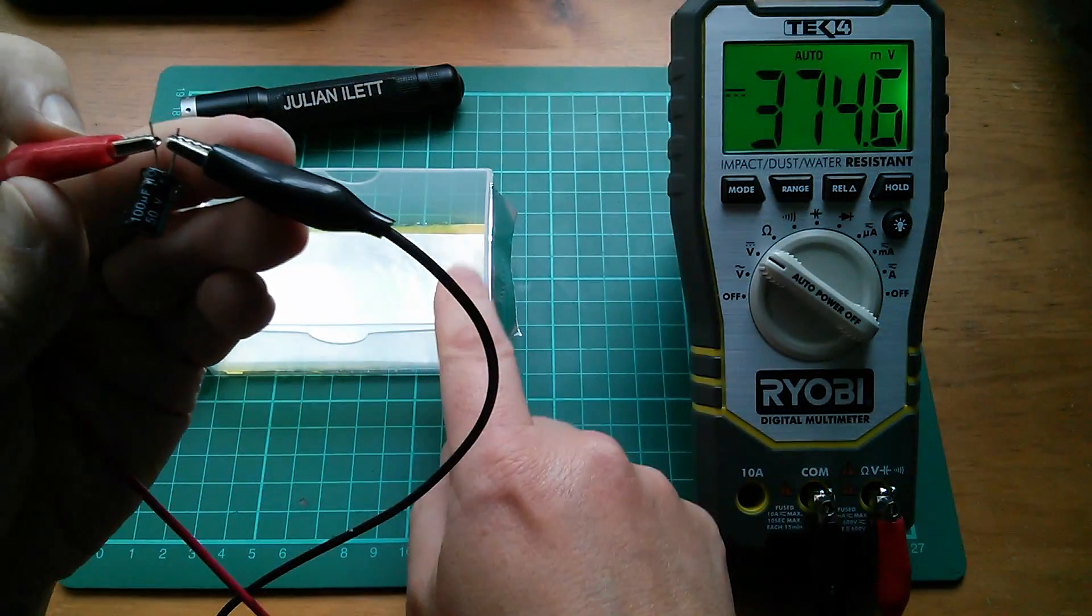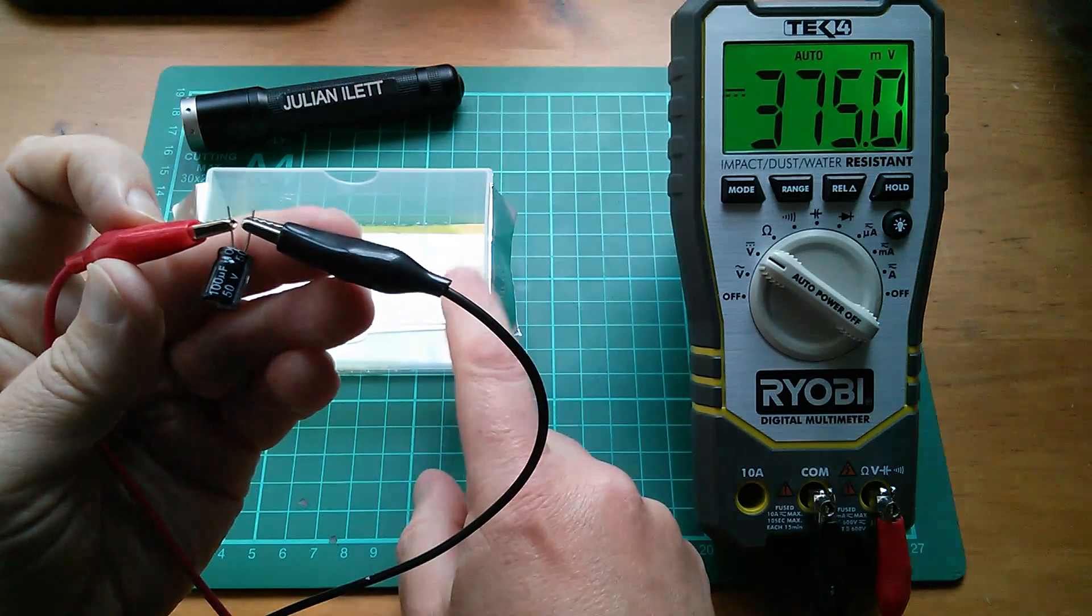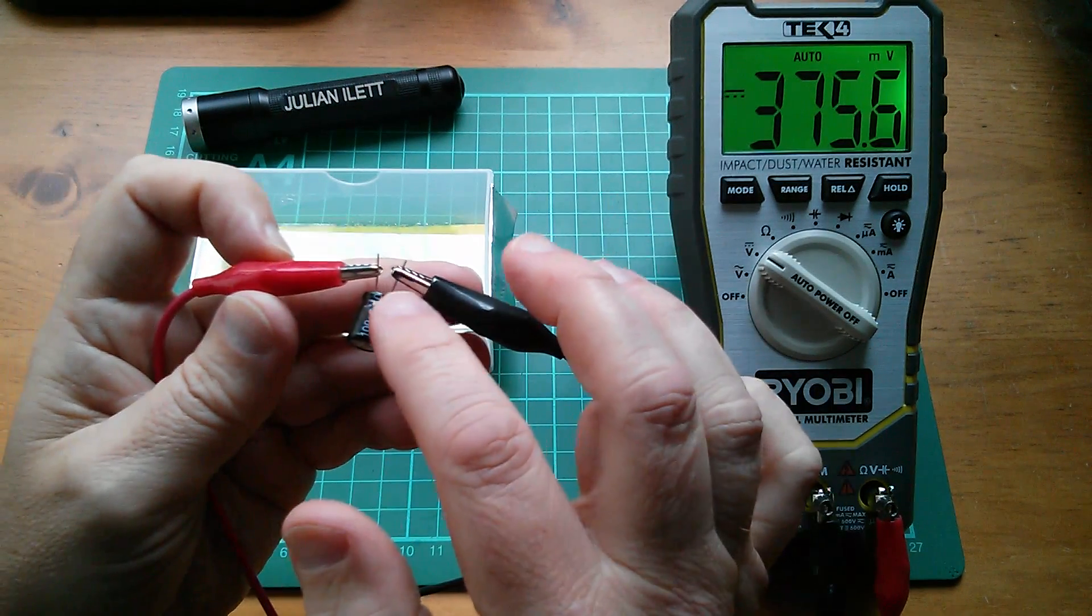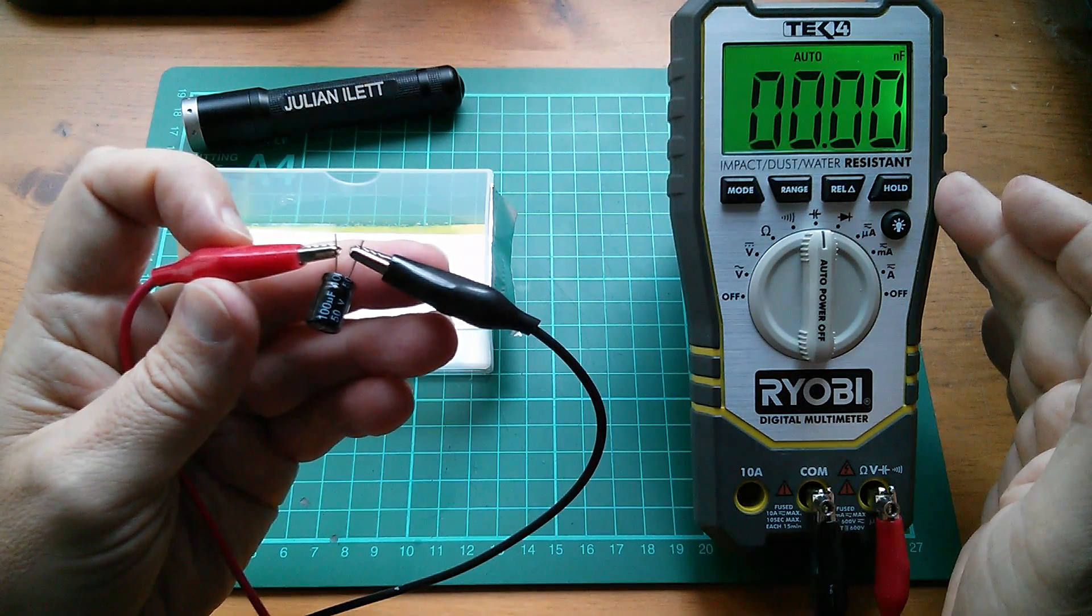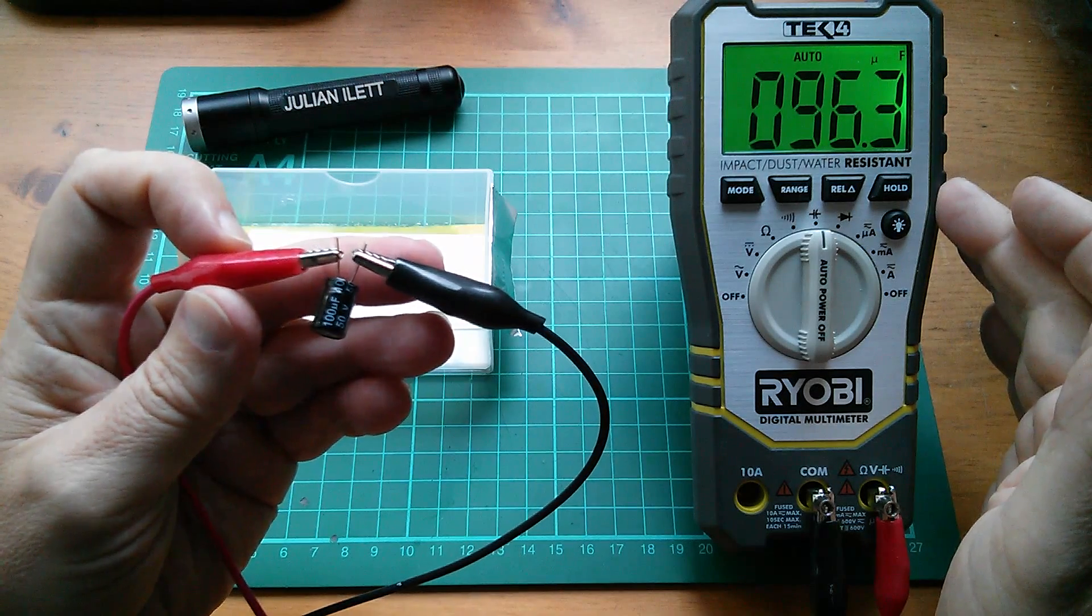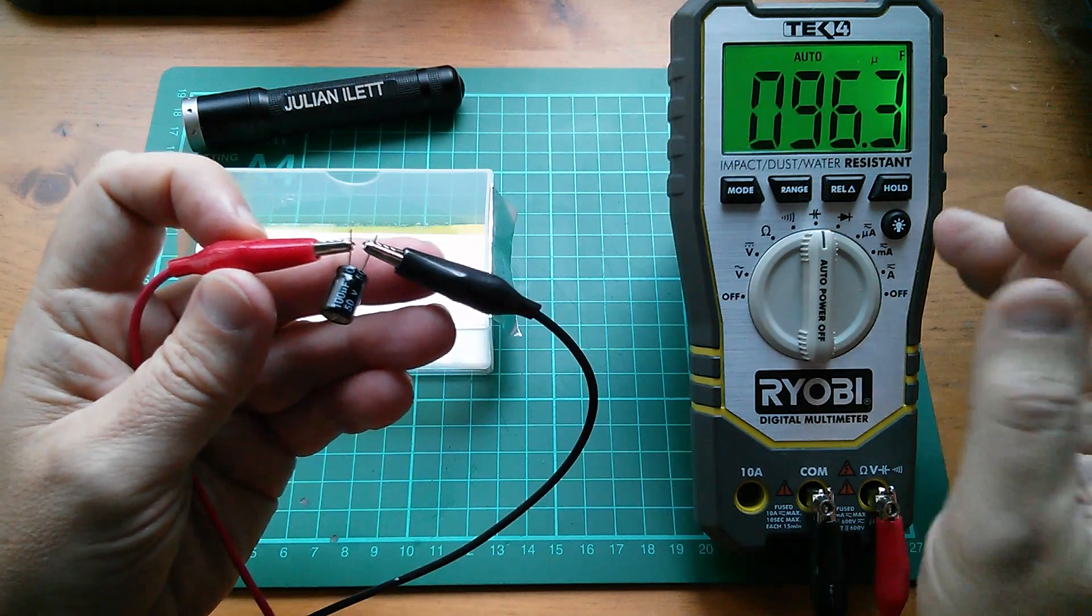But if this capacitor is genuinely a similar value, 60, 70 microfarads. And this is 100 microfarads. Let's just check that. This meter does take a while to register higher value capacitors. It only goes up to 100 microfarads. This is 96.3.